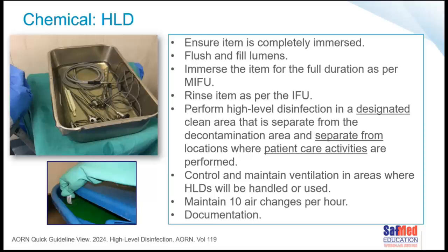Rinsing off afterwards. And the AORN also states that high-level disinfection needs to be performed in a designated clean area that is separate from where you clean, and separate from where the patient care activities are performed. We should be doing this in a controlled area where ventilation is maintained and that there are a minimum of 10 air changes per hour.